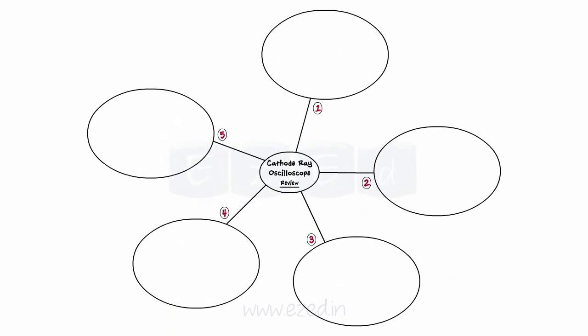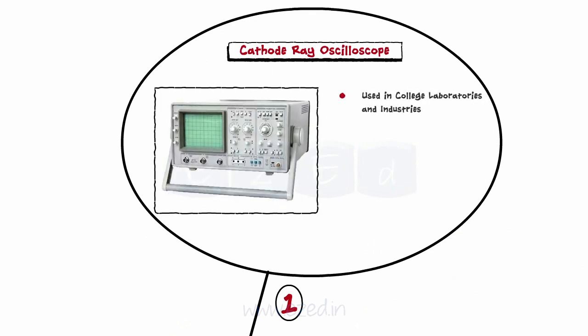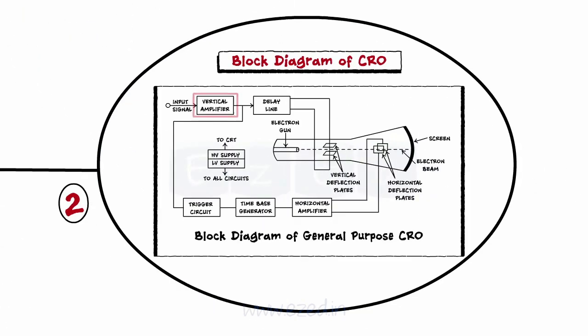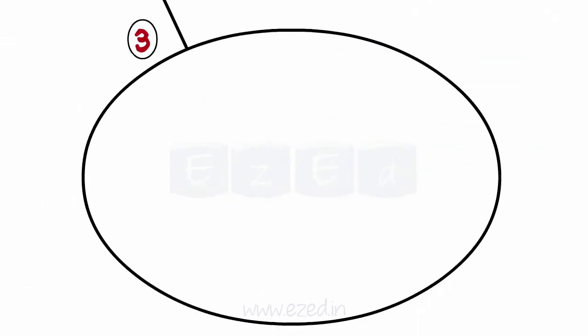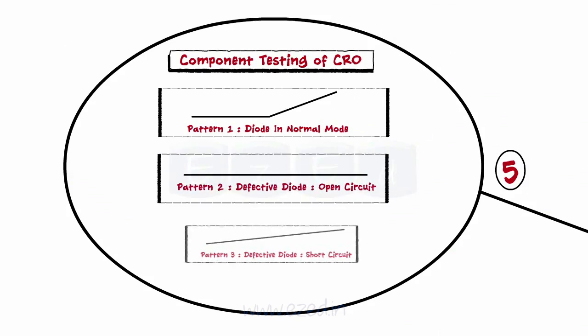Let's take a quick review of what we have learnt in this lecture. A CRO is an electronic instrument very commonly used in college laboratories and industries to analyse circuits by plotting different waveforms. The different blocks of CRO are vertical amplifier, delay line, trigger circuit, time base generator, horizontal amplifier, and cathode ray tube, CRT. Cathode ray tube is the heart of a CRO, consisting of three sections: electron gun assembly, deflection plates, and phosphor screen. We also learned measurement of voltage using the volt per division knob and measurement of frequency using the time per division knob. Lastly, we studied component testing using CRO, wherein we analysed a diode with three different patterns.